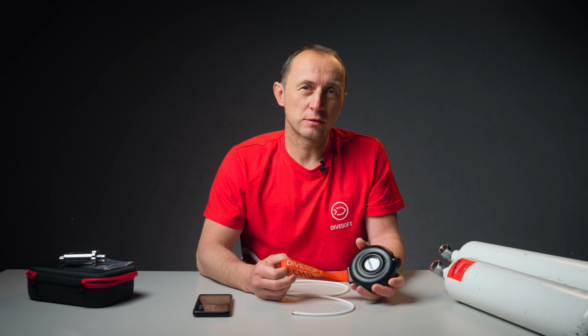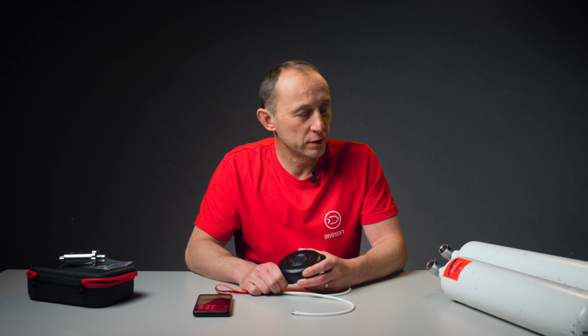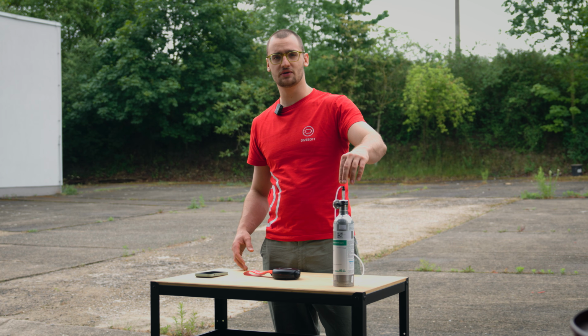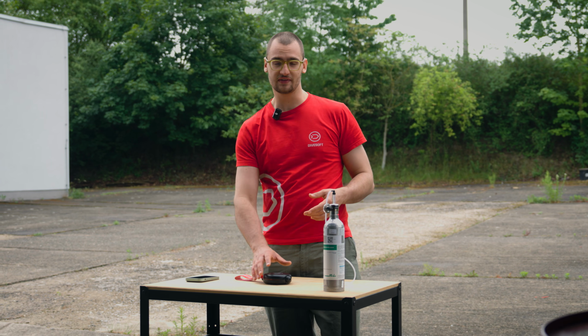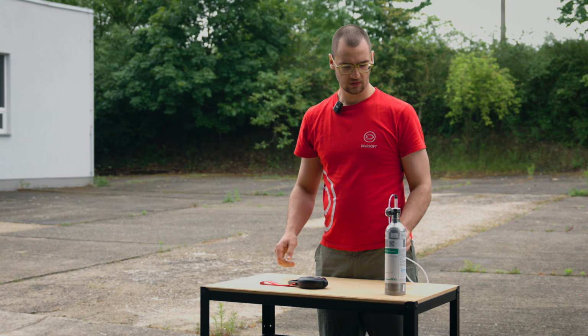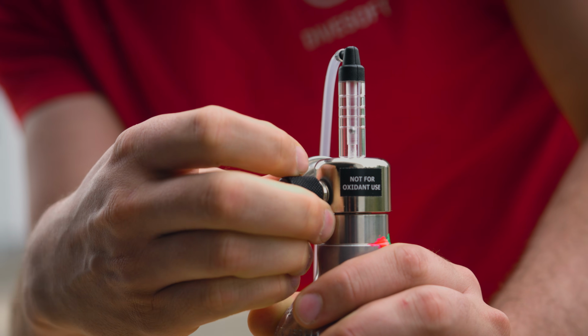One of the very important and brilliant features of the Echo Analyzer is CO detection. Carbon monoxide is a very dangerous gas, which you can't smell, you can't see, but it can affect your life or health. So it's good to know if it's present in your cylinder or not. We have very clean gas at Divesoft, but let's try it a little bit differently. Now we're outside because we're going to use a gas containing carbon monoxide to see the ability of the Echo to detect bad gas. Now I'm going to open the cylinder with the carbon monoxide.